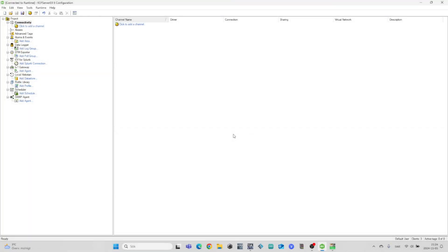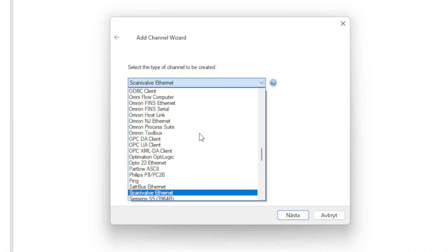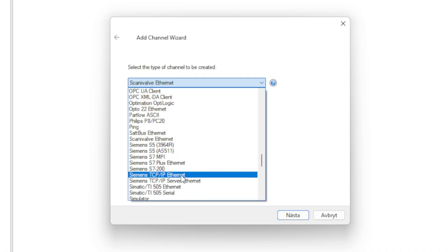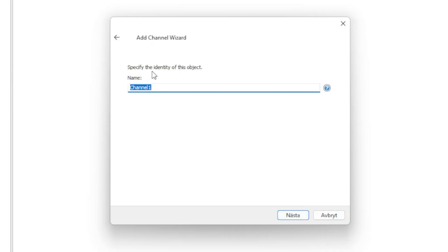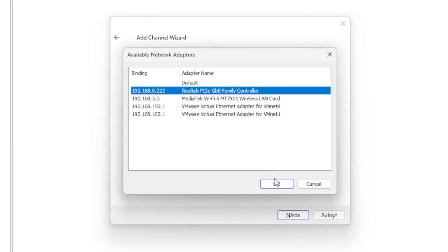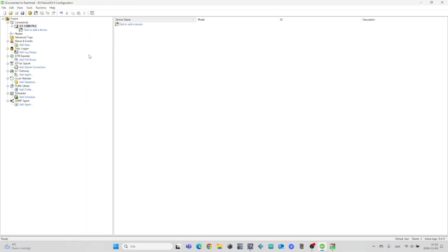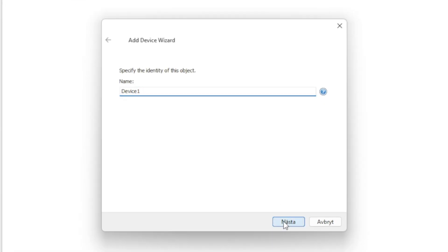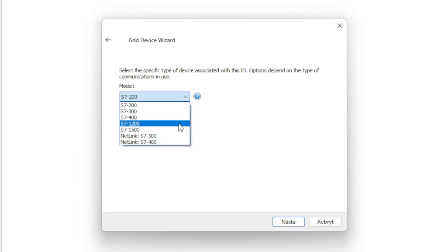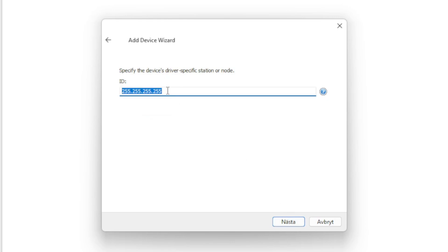In Kepware KepServer EX we want to add both our PLCs to the project. First we click on add a channel, then we choose Siemens TCP IP Ethernet. We also need to choose our computer's network card as the network adapter. Now to add a PLC we click on 'click to add a device', then we choose the correct PLC model, then we need to specify the PLC's IP address.